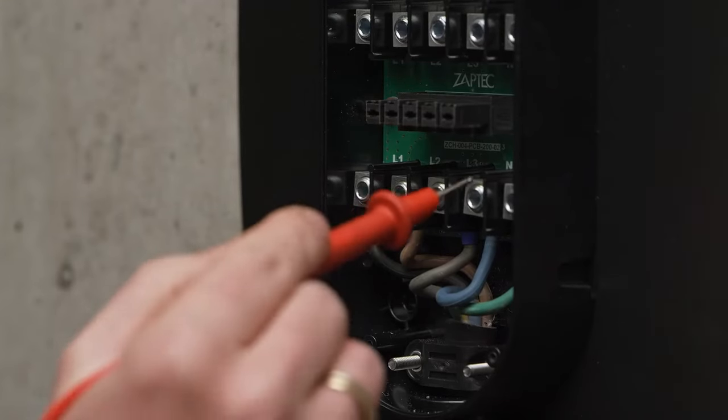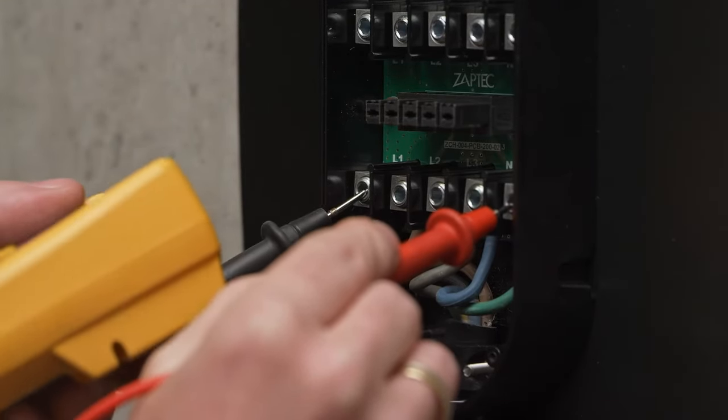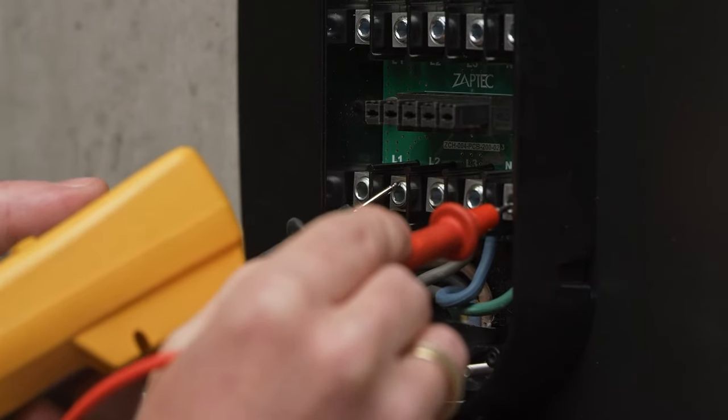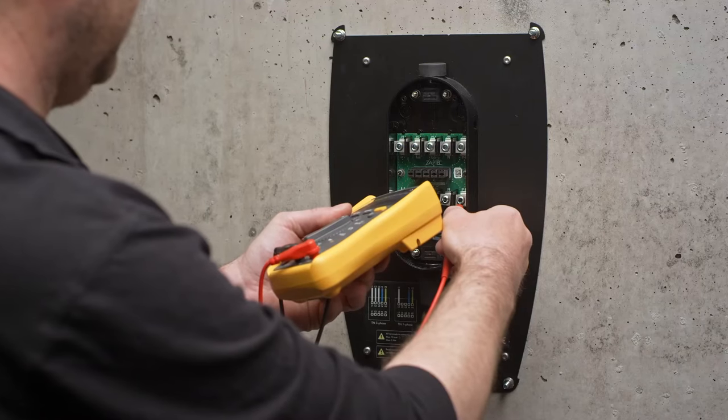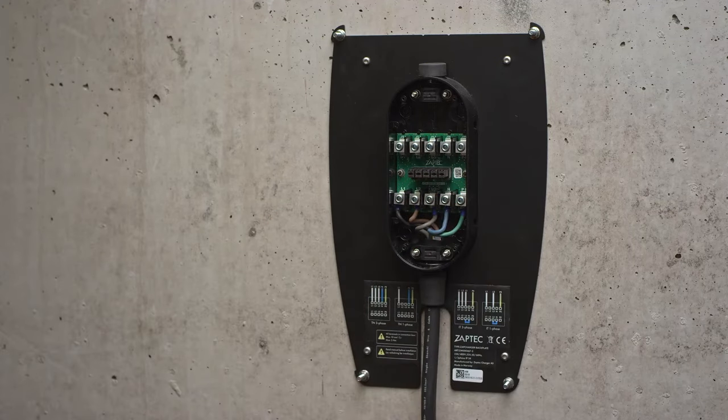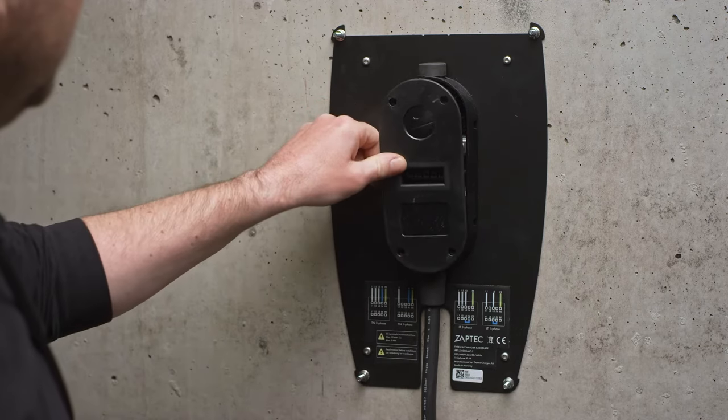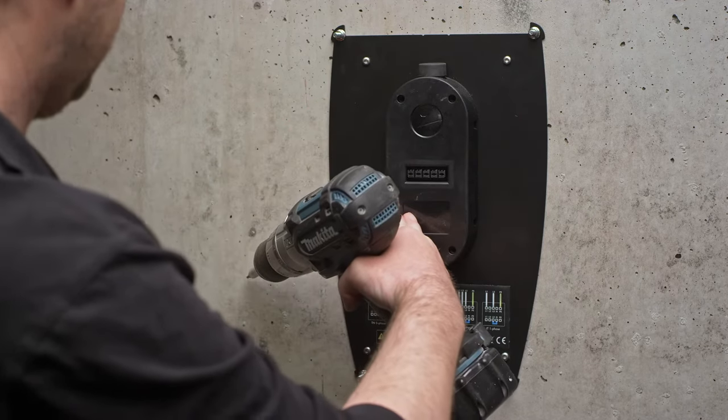It is important to take the necessary readings before placing the cover on the junction box. Do not insert measuring pins, wires, or other items into the quick coupling on the back plate. Voltage testing must be performed directly on the coupling screws.